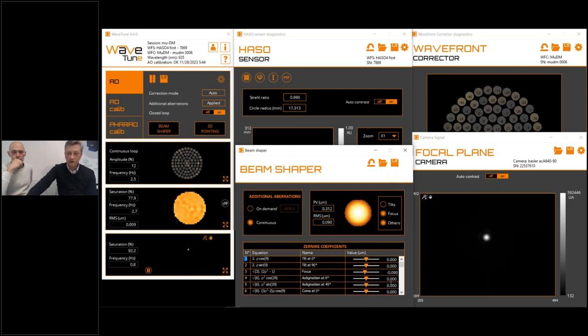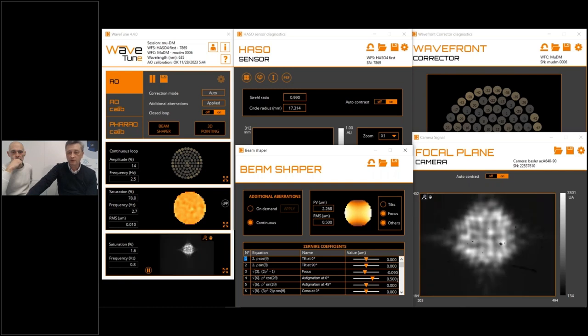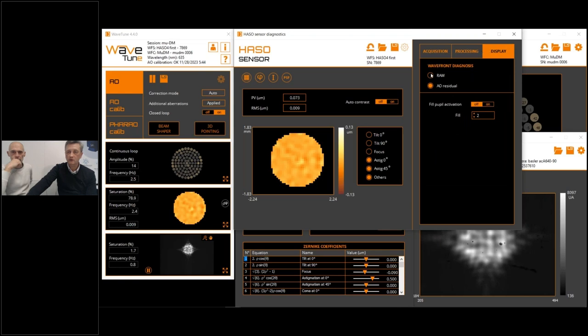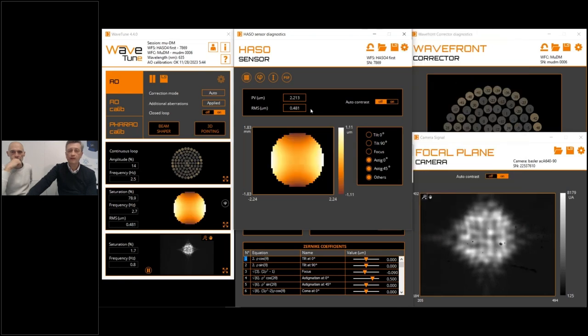To further illustrate the linearity, we apply 500 nanometers RMS of astigmatism. The mirror applied 500 nanometers RMS of astigmatism, and we measured a very close value of 480–485 nanometers — really very close to the proposed value.